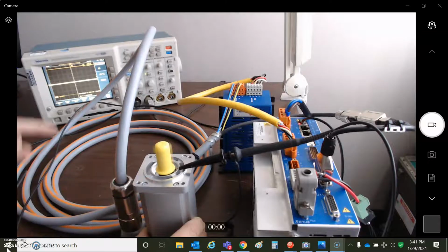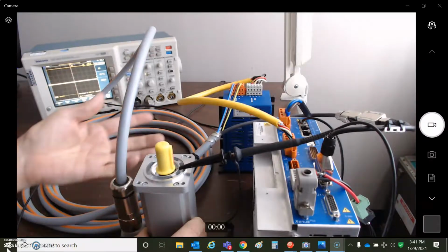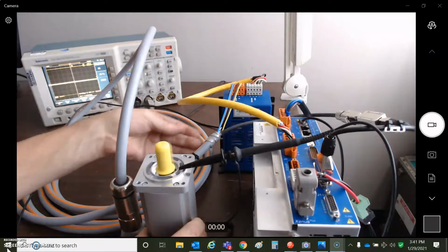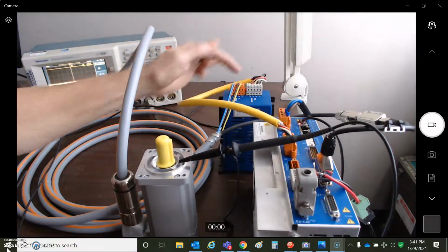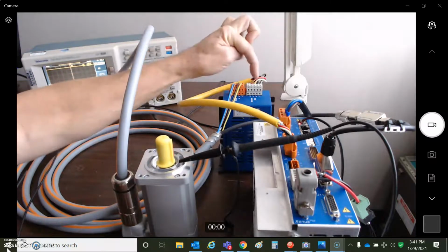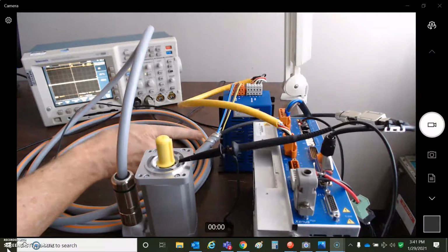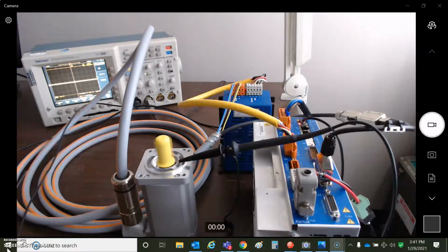Motor spinning. There's no PWM noise. I don't even have the outer shield. This is the worst possible. No case to earth. No outer shield to earth. The feedback's connected. That's good. But I'm using the Xenus Edge filter. So out of the drive, into the filter, out of the filter, down to the motor. Differential and common mode choke. So the common mode noise and the edges are knocked out with the filter.